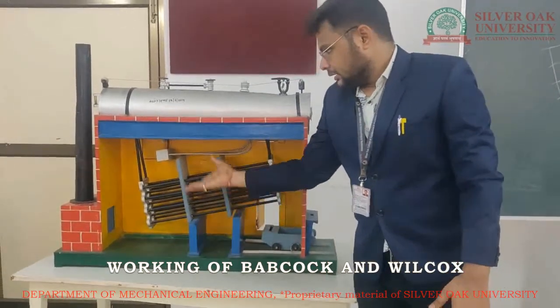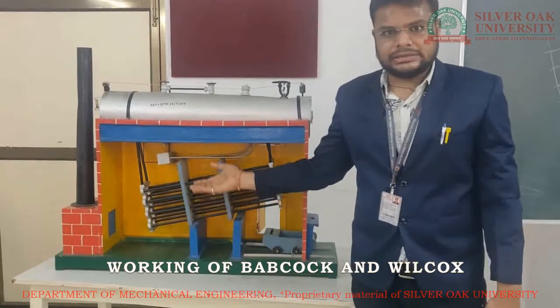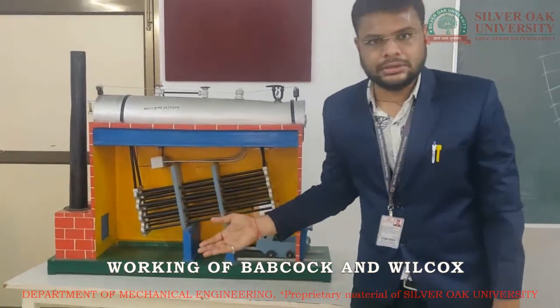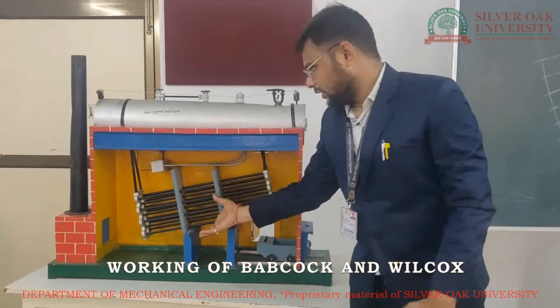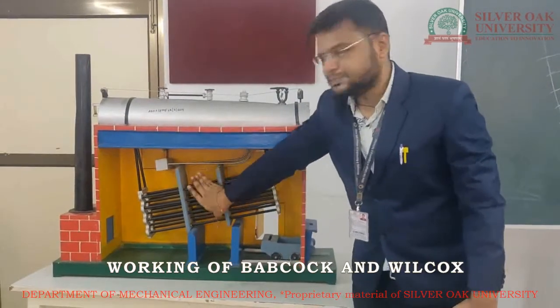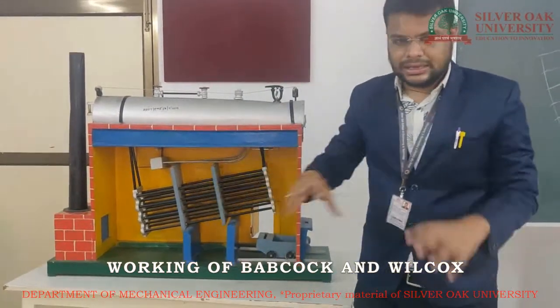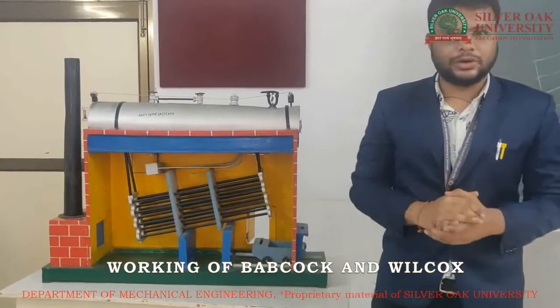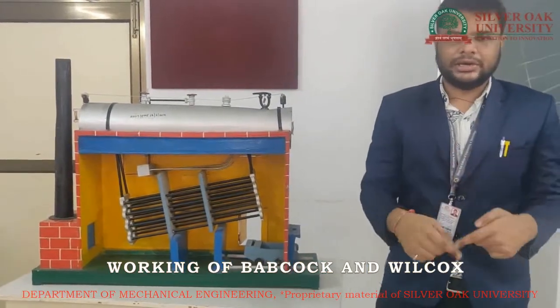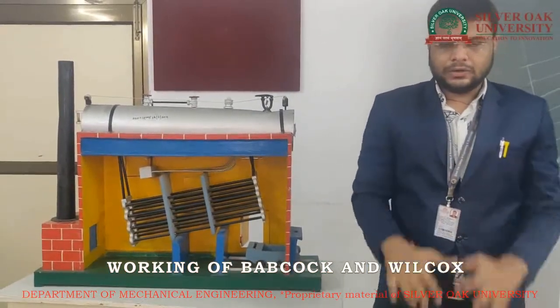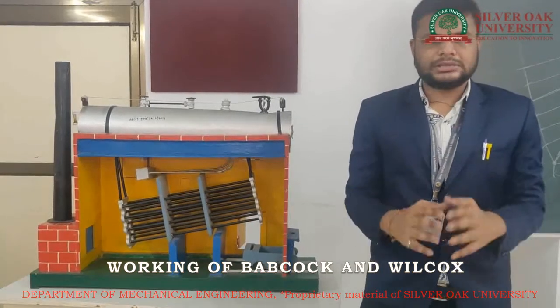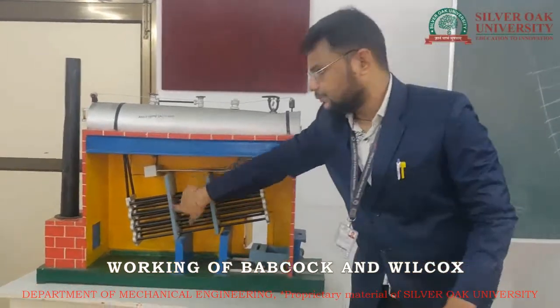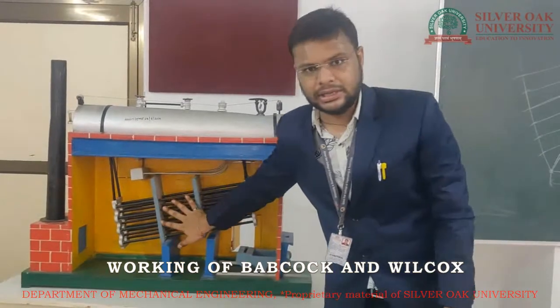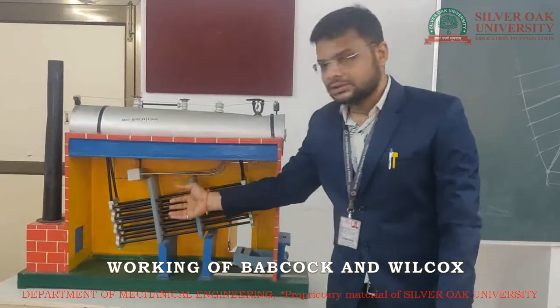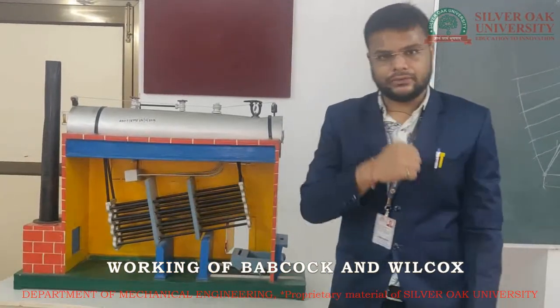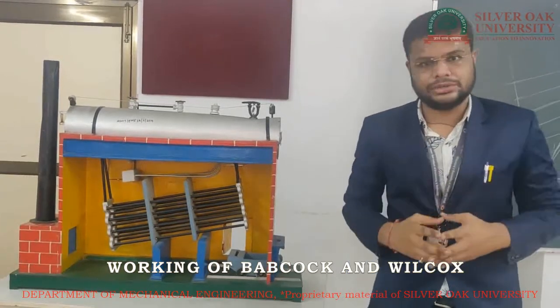Now here, the hot flue gases start moving in the upward direction. The hot flue gases cover only this particular area, so in order to increase the flow area of the hot flue gases and to convert the flow into the sine wave form, we have the baffle plates which are placed over here. Now whenever the water comes in contact with the hot flue gases, the water starts converting into steam.